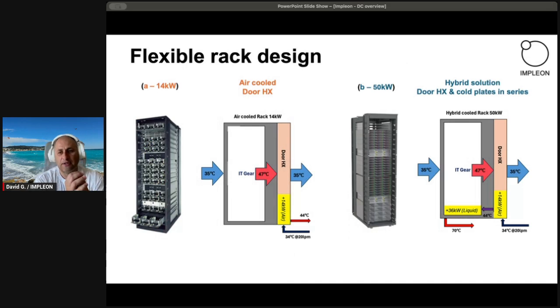And this is how we present that. In the first stage, we can use only door heat exchangers. By this, we take away the raised floors, hot aisles, cold aisles, etc., and are able to cover 14 kilowatt racks with a flow rate of 20 liters per minute. And the same flow rate will apply for 50 kilowatt racks. We will just serially connect the liquid heat transfer, which will add another 36 kilowatt and allow us to achieve 50 kilowatt per rack. But the flow rates remain the same, and the infrastructure remains the same.